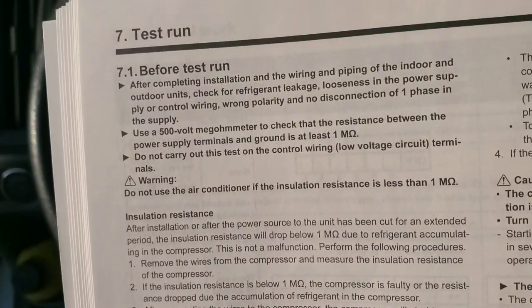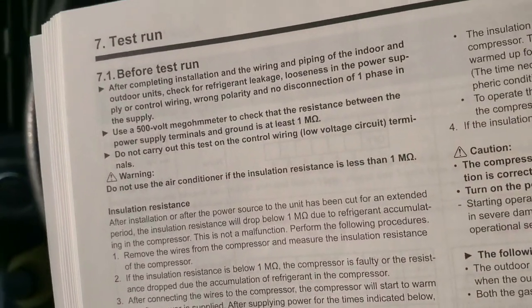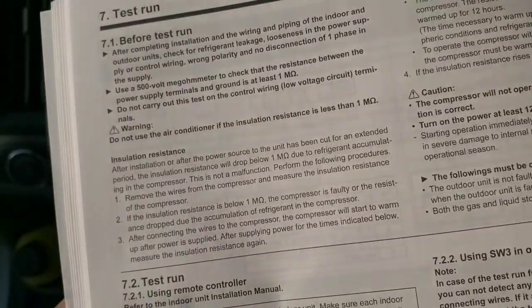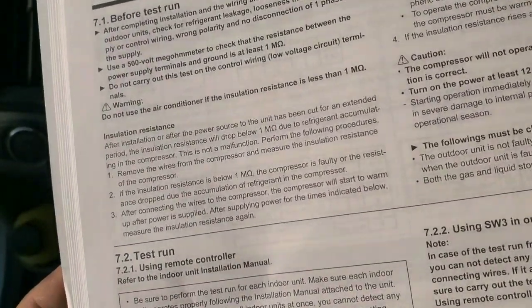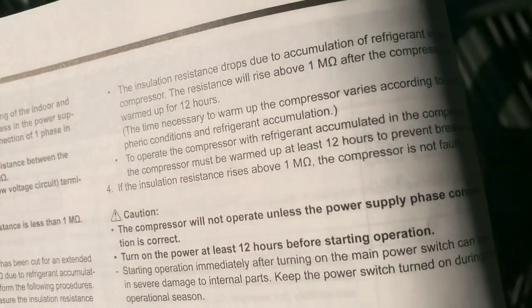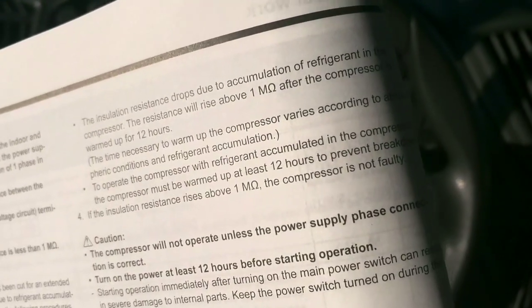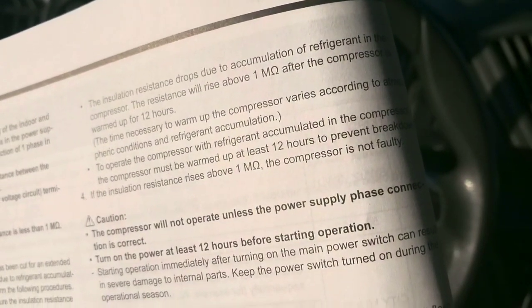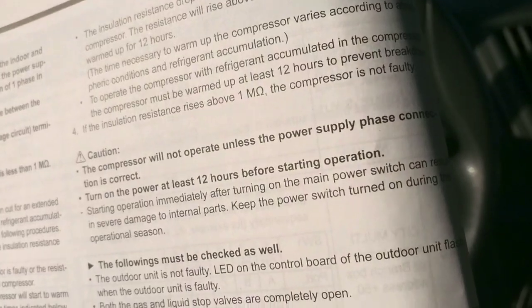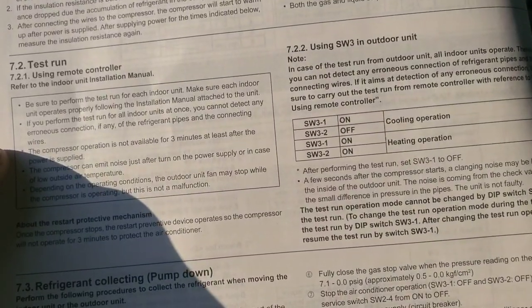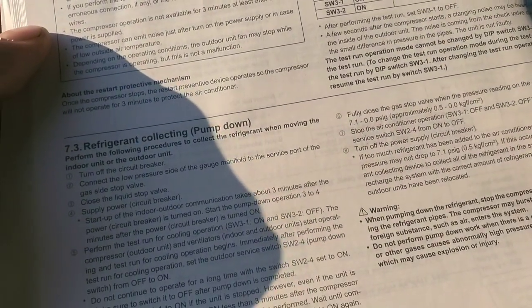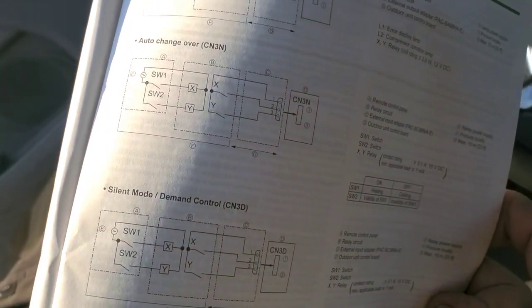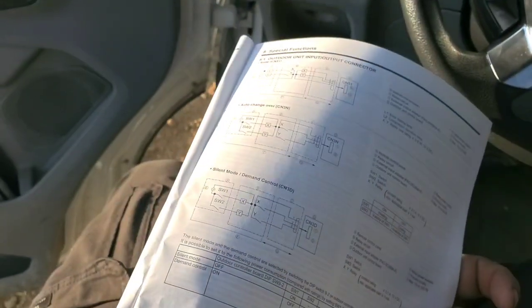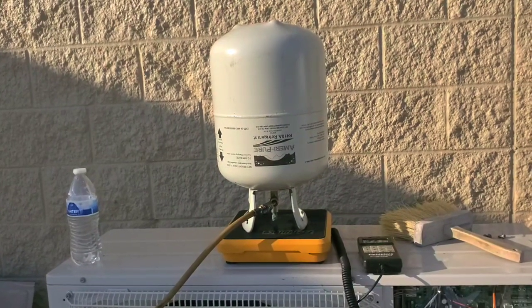500 volt mega ohmmeter between the power supply and ground. A whole bunch of bullshit about that, and then we got the insulation resistance of the compressor, and you know, this whole 12-hour warm-up thing, and it's just a bunch of engineering crap. They want you to start it up in a laboratory setting, basically, which is very unrealistic. We're just going to turn it on and add 8.44 pounds of refrigerant.